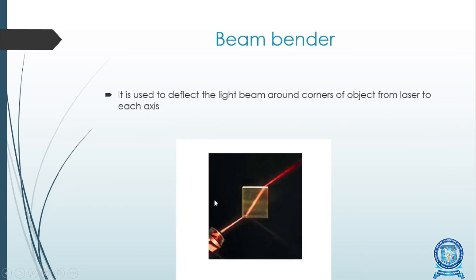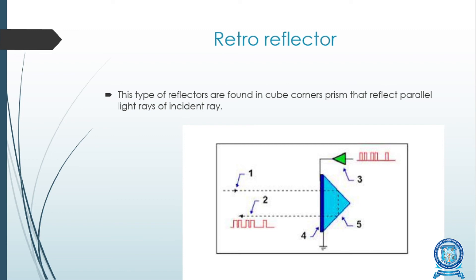The second optical element is the beam bender. From the figure we can see clearly that the beam bender receives a beam from one area and bends it to another area, directing the light beam around corners of the object from the laser to each axis. The third optical element is the retro reflector, which reflects a beam back parallel to the incoming beam — the beam travels from one point to the retro reflector and is reflected back in the same direction.